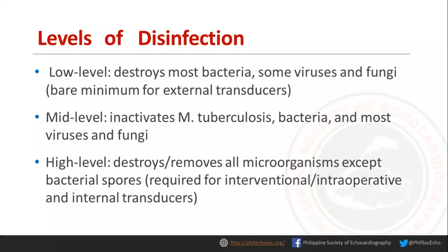And high-level disinfection destroys all microorganisms except bacterial spores. So it is required for critical items or objects that enter sterile tissue, or for semi-critical items that come in contact with mucous membranes, such as endoscopes, including our TEE probes. We can use glutaraldehyde and hydrogen peroxide-based formulations.